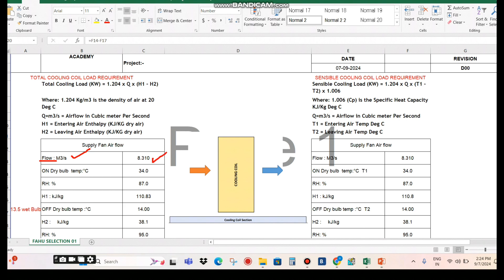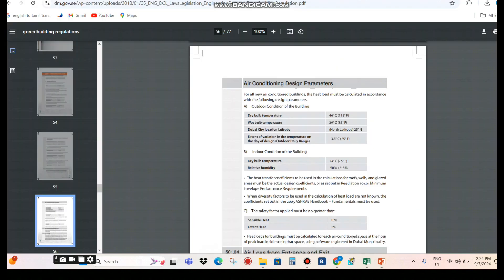Coming to the important point — the on-coil dry bulb temperature. Here I consider 34°C, and I'll explain why. If you see the Dubai Green Building Regulation, for an air conditioning design based in Dubai, the dry bulb temperature to consider is 46°C (115°F) and the wet bulb temperature is 29°C (85°F). However, for FAHU design we don't normally consider 46°C and 29°C — we consider 34°C and 32°C. I will explain the difference between these two considerations for FAHU selection.